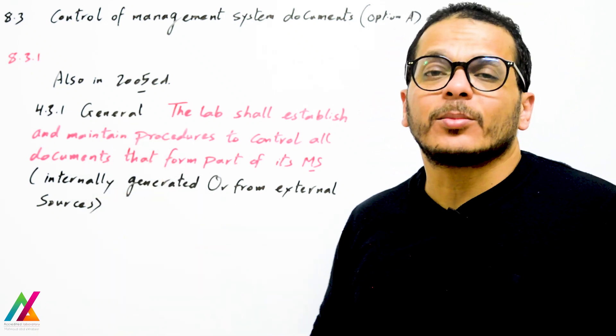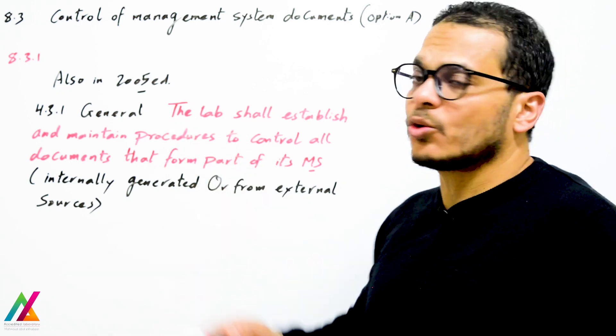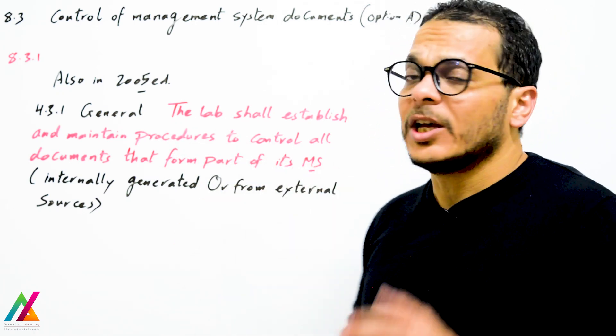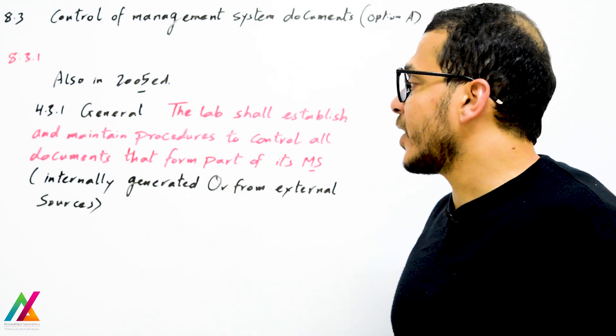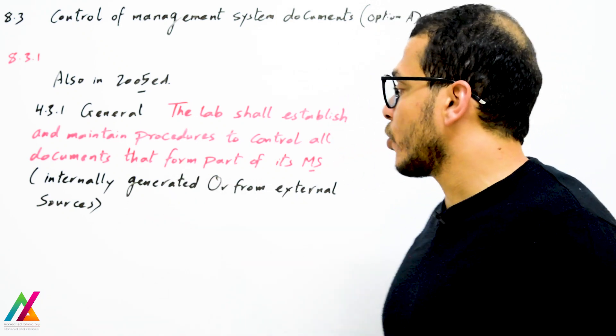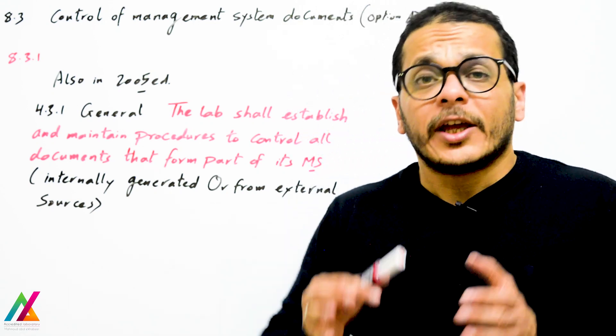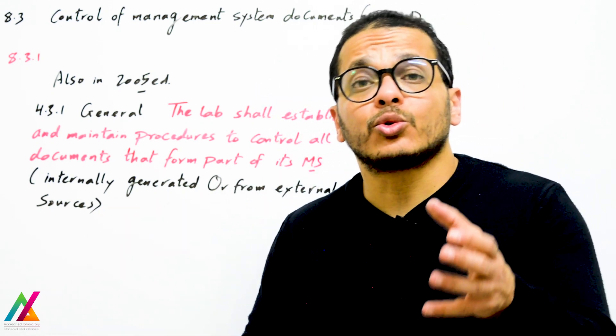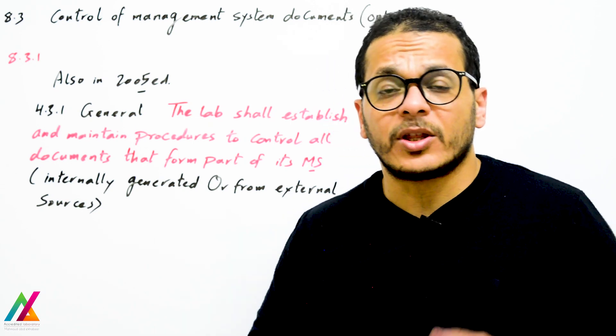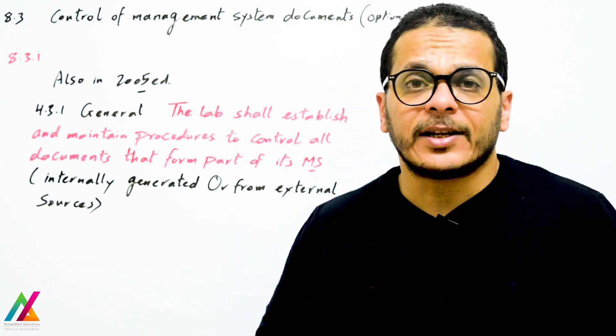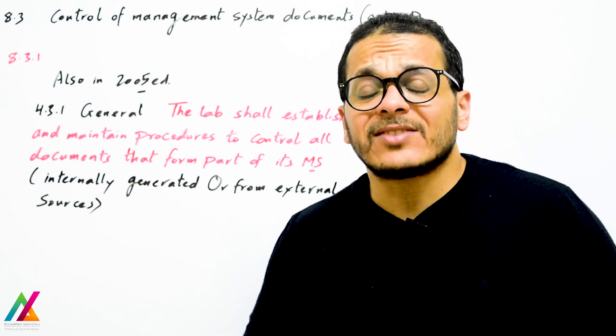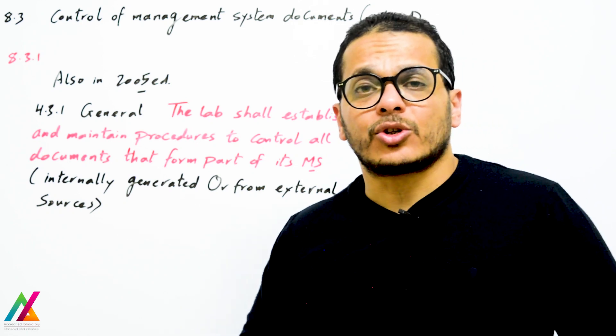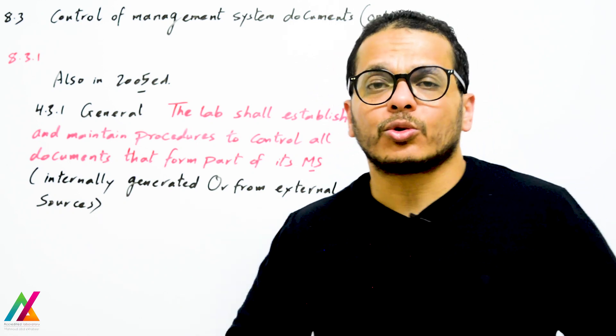In the 2005 edition, clause 4.3.1 stated the lab shall establish and maintain procedures — it was mandatory to prepare a procedure to control all documents, whether internally generated or from external sources. But in the 2017 edition there is more flexibility: you don't need to prepare a procedure, you just need to find a way to control your documents.